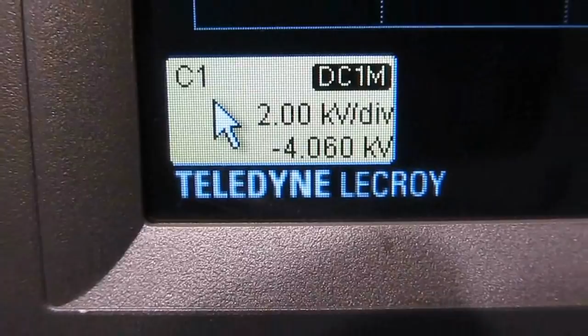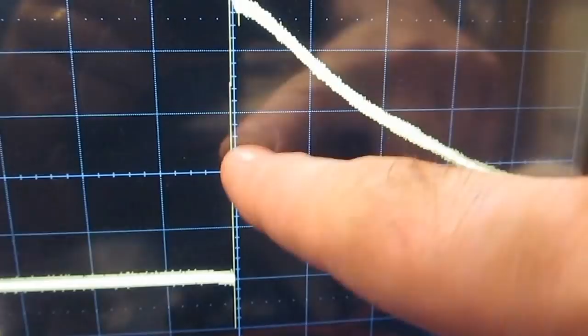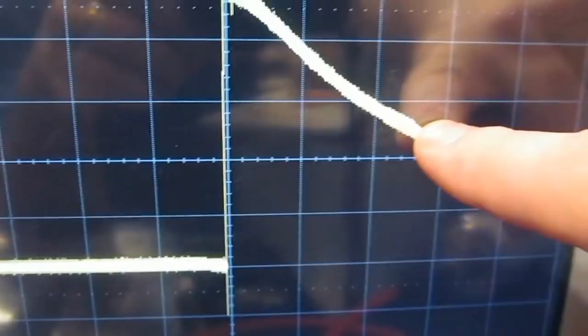So I've gone ahead and changed our generator. You can see we're still at 2000 volts per division, but now I have roughly a 4000 volt offset, and we're at 20 microseconds per division. So we're currently 5 divisions up, or 10,000 volts, and 2.5 divisions up would be here, roughly 2.5 divisions out, or 50 microseconds. Alright, again I'll be applying 5 transients.